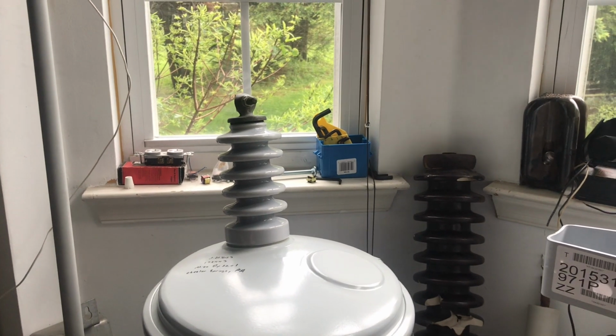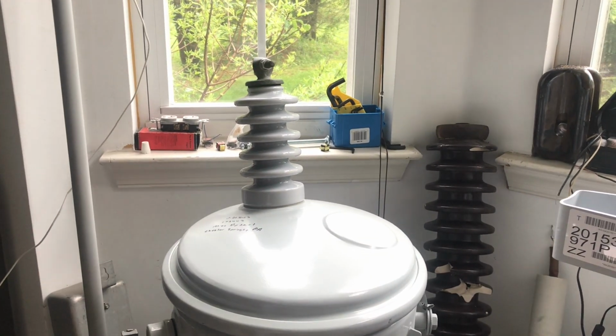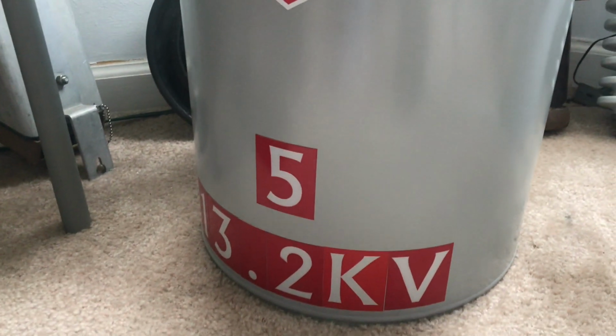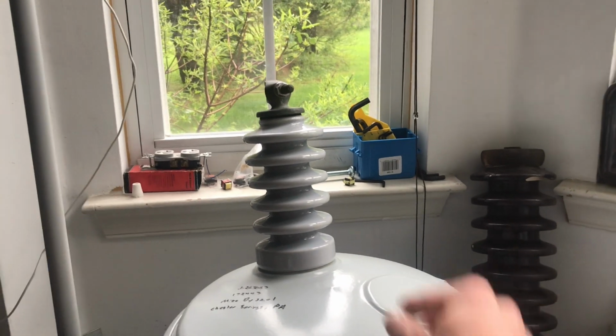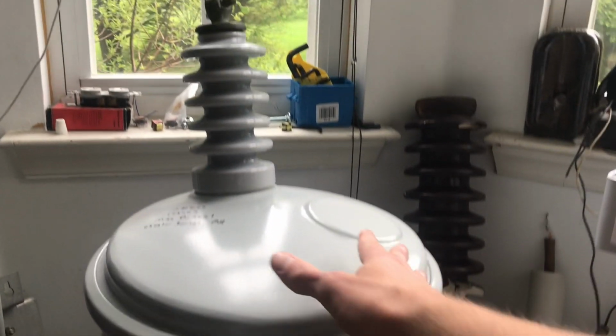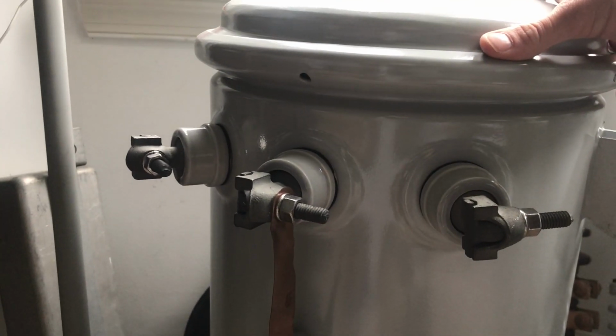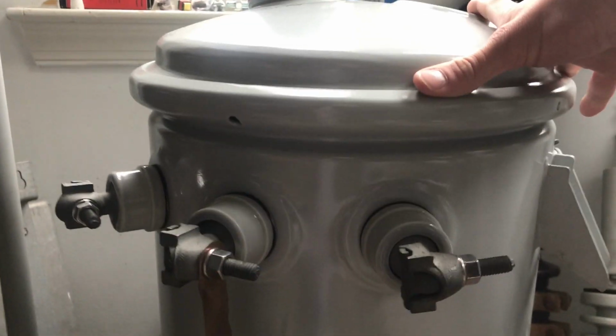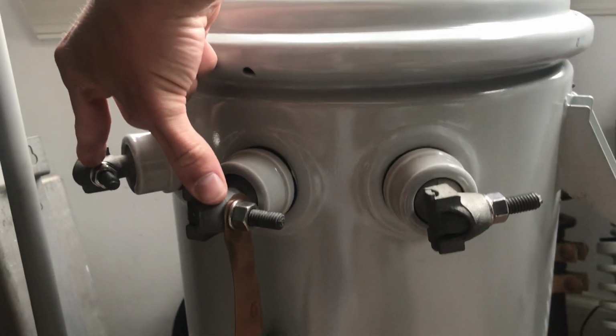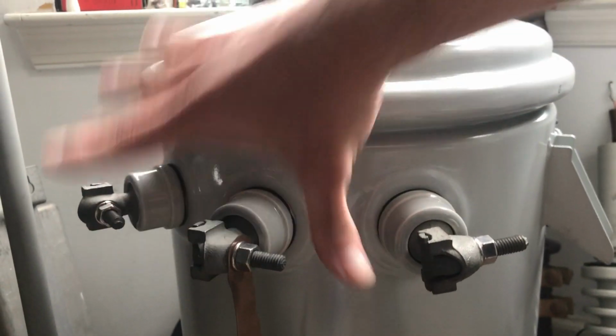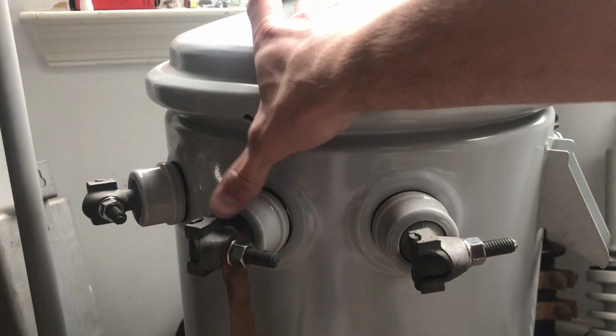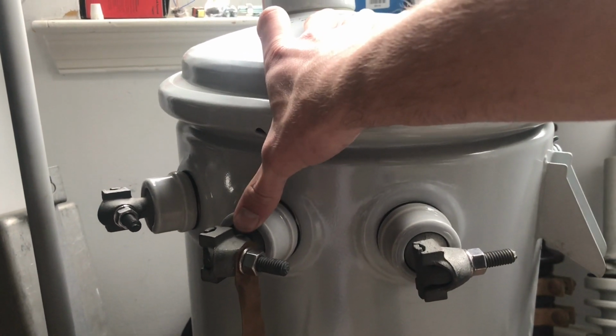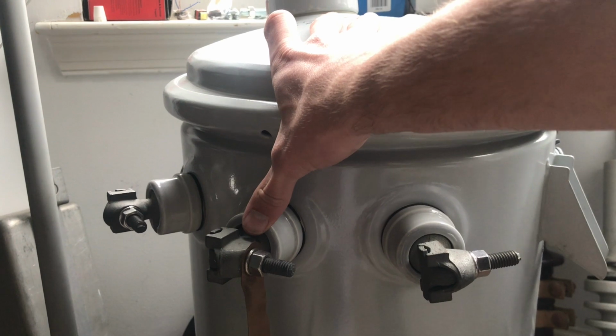As you can see, one single bushing on top, which is where, in this case, since this is a 13.2 kV transformer, a 7620 volt line would come in and then go to ground. Single phase, but there are 3 low voltage bushings. Each are 120, 120, 240. A lot of people refer to this as the center tap. However, this is not a center tap in the transformer.